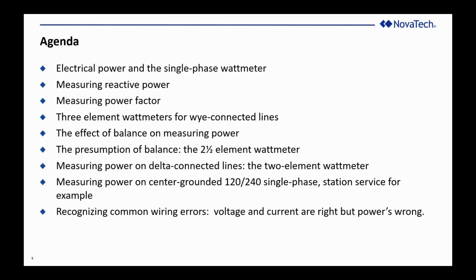We're going to start at the very bottom, but we're going to move fast. We're going to talk about electrical power and the single-phase wattmeter, develop measurement of reactive power and power factor. We'll transition from single-phase to three-phase, talk about Y-connected lines, the importance of balance regarding the measurement of three-phase power. I will go off on a little tangent about the 2.5 element wattmeter to illustrate the importance of balance. And then we will develop how delta connected lines only require 2 single-phase wattmeters or a 2-element three-phase wattmeter to measure the total power.